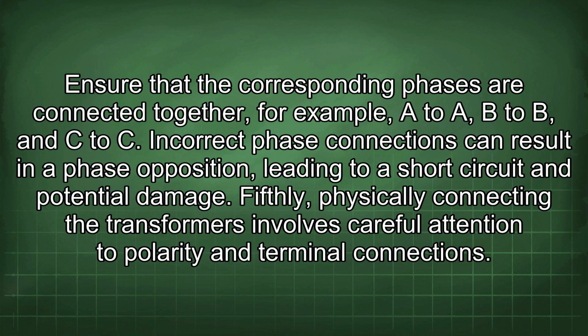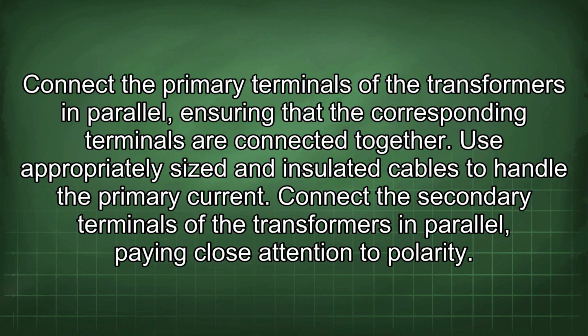Fifthly, physically connecting the transformers involves careful attention to polarity and terminal connections. Connect the primary terminals of the transformers in parallel, ensuring that the corresponding terminals are connected together. Use appropriately sized and insulated cables to handle the primary current.